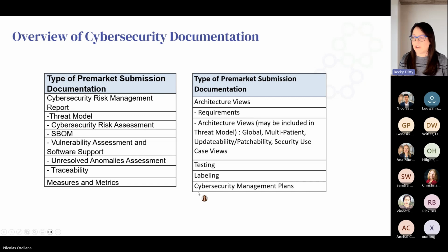Additionally, you have to have cybersecurity management plans, which is how you're going to manage cybersecurity overall and in the post-market world. FDA requires you to have, actually regulation requires you to have two processes, an ongoing regular cycle of updating your software. For some people, this may be quarterly, maybe every 6 months or annually, but then there's an out of cycle update, and that is when you find a cybersecurity vulnerability that you need to address. How quickly are you going to do it? What's your plans for that? What's the timeline? Both of those cycles need timelines associated with them. And you also need to identify how you're going to communicate that information and those patches to your users.